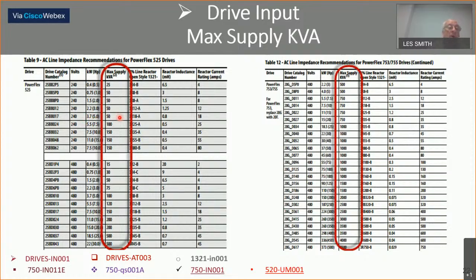it says the transformer, the maximum kVA would be 50 kVA for it without using anything in front of it. Anything bigger than that, you would use a line reactor, and there's the part number, which would mean it'd be an 18 amp reactor. Over here, let's take a look at a 5 horsepower and see if we can find it here. Okay, 5 horsepower on a 753. Now, it is the maximum supply you can put on that, so 500 kVA. Now, I believe the other one was 100 kVA. There's 5 times the size there, and that has to do with the inductor that's between the converter and inverter. That is in the 755.